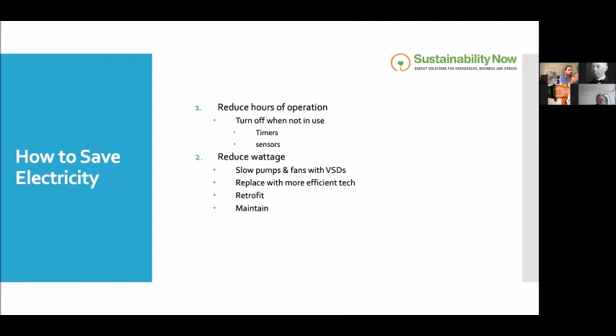So reducing wattage, Vasily has talked about this before. Variable speed drives are a great way to do that. Slowing those pumps or centrifugal pumps or fans down by 20% will result in around about a 50% power saving. Just simply replacing old electric motors with modern ones could save in the realms of 30 to 40%. So that as well. Similarly with lighting, replacing old fluorescent lights with new LED technology might save you about 60%. Retrofitting of existing plant, and just simply maintaining it, making sure it's running properly and smoothly, and not falling apart is another way.